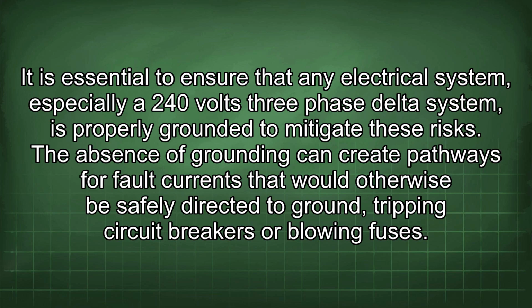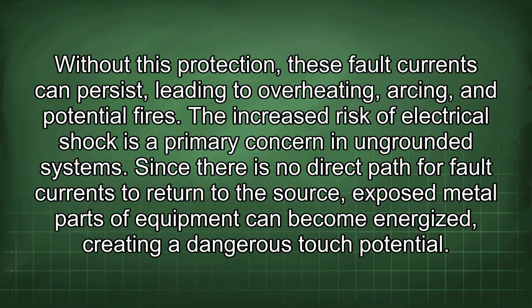ground, tripping circuit breakers or blowing fuses. Without this protection, these fault currents can persist, leading to overheating, arcing, and potential fires. The increased risk of electrical shock is a primary concern in ungrounded systems. Since there is no direct path for fault currents to return to the source, exposed metal parts of equipment can become energized, creating a dangerous touch potential.